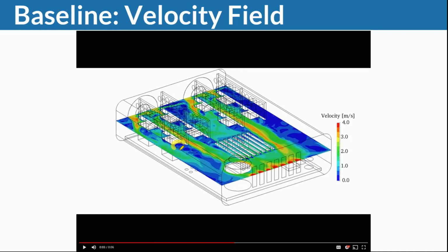We can also see that here we have some blue areas where not a lot of air movement is going on. And we can see in a second what's going to happen there. Here it's actually okay. Here it looks okay, but we can already get a feeling for how our air moves through this enclosure. Let me quickly erase that.